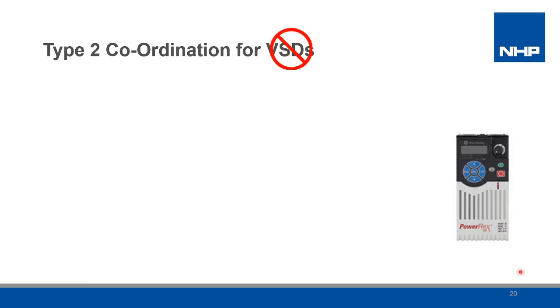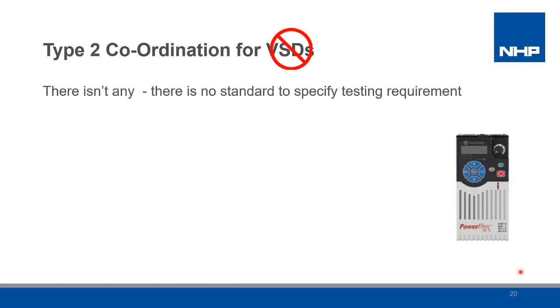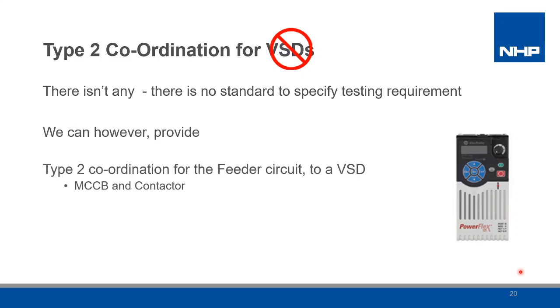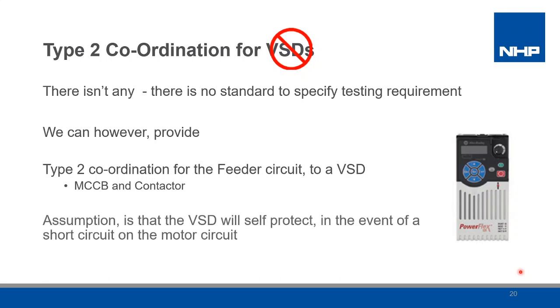There's a number of requests for Type 2 coordination tables for VSDs, but these do not exist. Type 2 is not defined in any standards associated for variable speed drives. Offering feeder circuit Type 2 with just an MCCB and contactor provides the same intent, reduced downtime on a fault. This is assuming the VSD self-protects under a short circuit or fault.